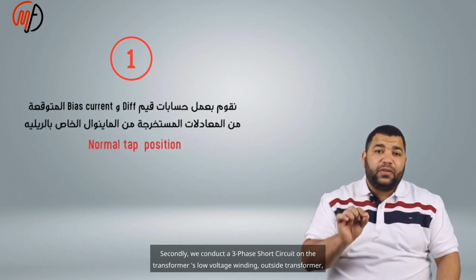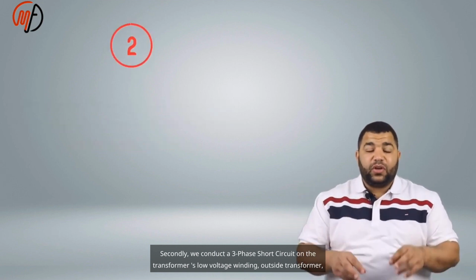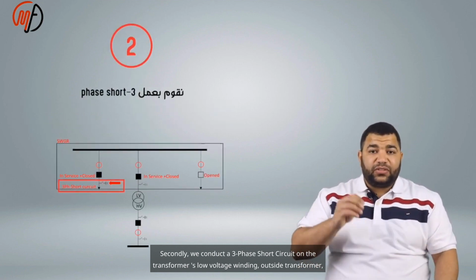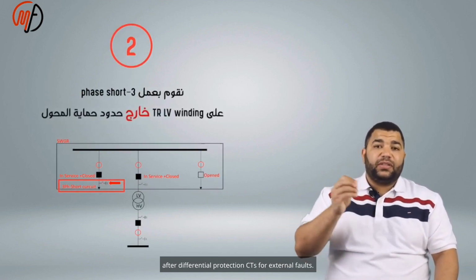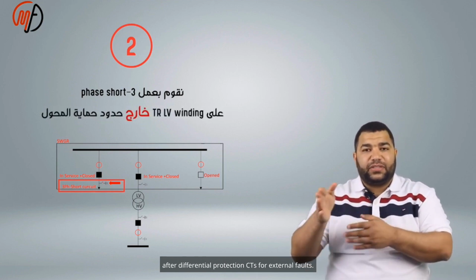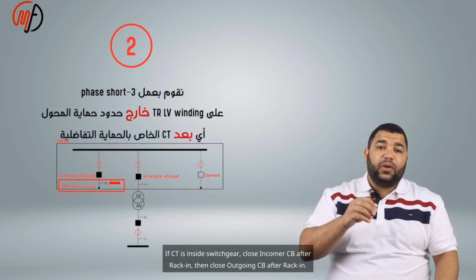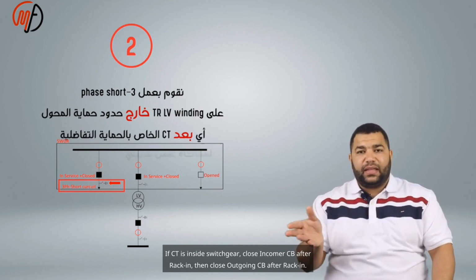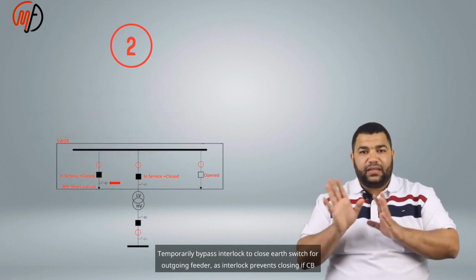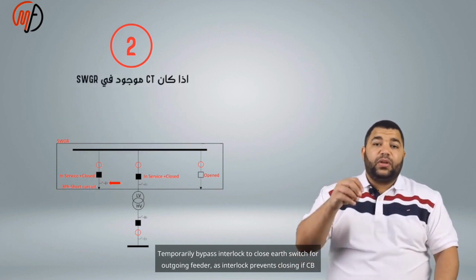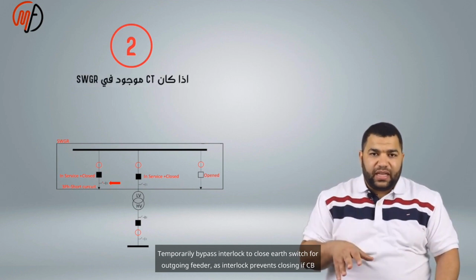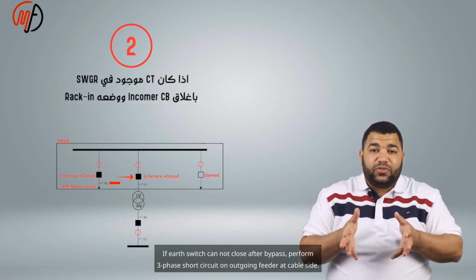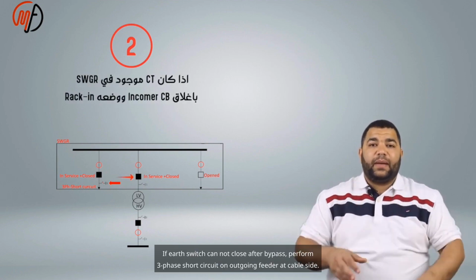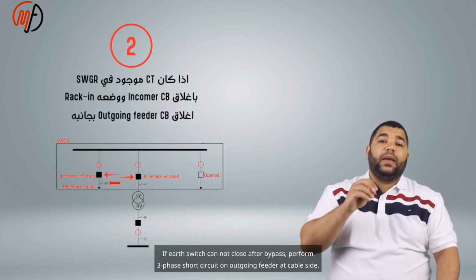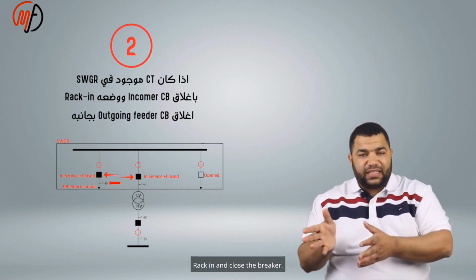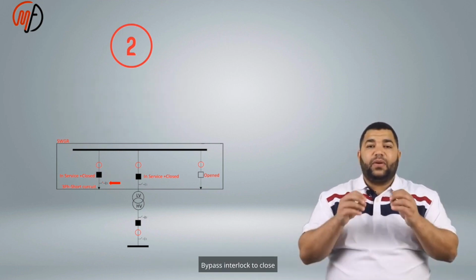Secondly, we conduct a three-phase short circuit on the transformer's low voltage winding, outside the transformer, after the differential protection CTs for external faults. If the CT is inside the switchgear, close the incomer CB after rack-in, then close the outgoing CB after rack-in. Temporarily bypass the interlock to close the earth switch for the outgoing feeder, as the interlock prevents closing if the CB is rack-in. If the earth switch cannot close after bypass, perform a three-phase short circuit on the outgoing feeder at the cable side. Rack-in, close the breaker, bypass the interlock to close.